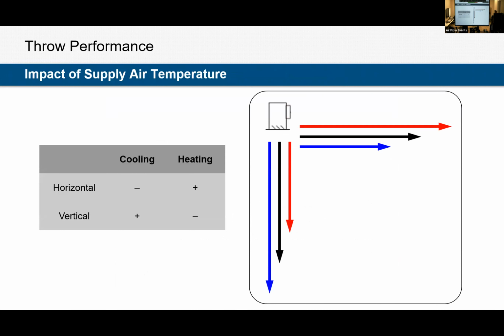Here's kind of a summary of that: when you're shorter in heating, longer in cooling, etc. Usually, I would say engineers are not designing with all of this in mind. But if you hit the wall and drop, it's a wash. It really might become an issue in weird situations where you've got two diffusers really close to each other, or a bulkhead or an obstruction that wasn't properly accounted for.